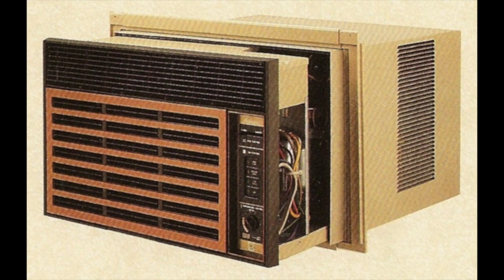That was exactly what it did last year too — towards the end of last year, that's what was happening. The condenser on that thing is shot; it's all rotted, breaking down, and decaying, and consequently the airflow is pretty abysmal. So I went hard on that condenser and got it at least 85% clear. The airflow improved drastically, and it's getting decent sub-cooling now through the condenser.